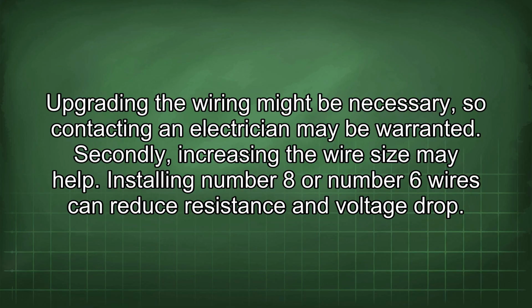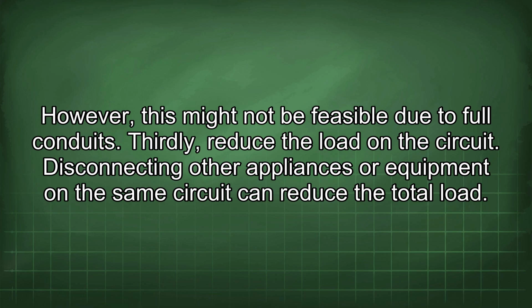Secondly, increasing the wire size may help. Installing number 8 or number 6 wires can reduce resistance and voltage drop. However, this might not be feasible due to full conduits. Thirdly, reduce the load on the circuit. Disconnecting other appliances or equipment in the same circuit can reduce the total load.